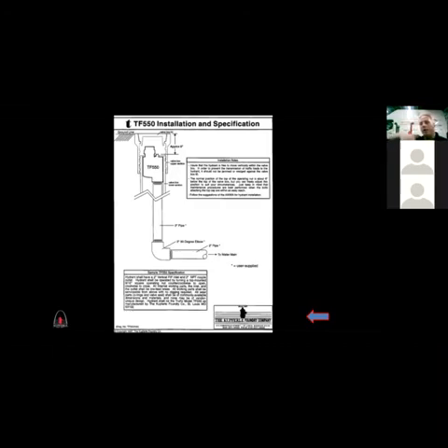I just don't have an operating rod and a plunger. I have a very short plunger and a very short operating rod that just fits into the housing of this particular device and just threads onto a 2-inch pipe that's a wet barrel all the time. So there's no weep hole with this one because you don't need it because of the freezing issue. There's no freezing issues in those particular parts of the country.